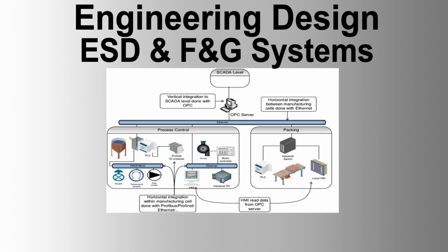I/O requirements. 1. General specifications. Each I/O module galvanically isolated from external circuits, capable of handling short circuits without affecting other I/Os. Maximum 16 points per module, protected against power supply polarity reversal. 2. Analog inputs. Capable of processing specified analog signals with 750 ohms load capability. Software configurable range supporting 0 to 20 milliamps range for fire and gas detector fault monitoring. Capable of processing signals from smart transmitters, supporting both 4-wire and 2-wire configurations. Open, short circuit, and out-of-range detection with results available for logic sequences.